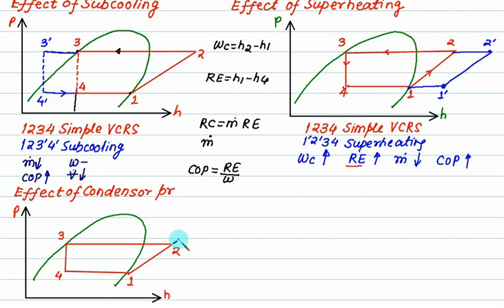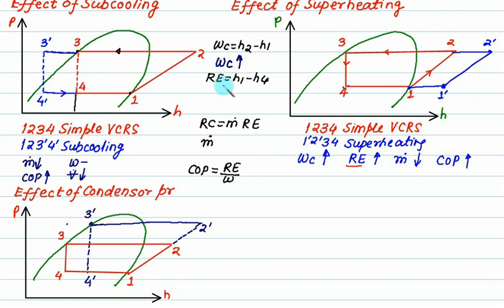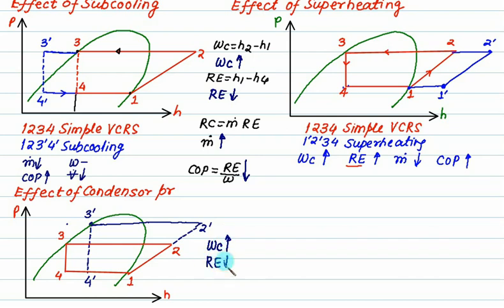If condenser pressure increases, state 4-dash shifts to the right. As a result, compressor work increases — which is not desirable. The RE, which was h1 minus h4, becomes h1 minus h4-dash, so RE decreases — also not desirable. Since RE decreases, for the same RC the mass flow rate increases. The COP decreases, and additionally the compressor discharge temperature T2-dash is greater than T2, which is also undesirable.